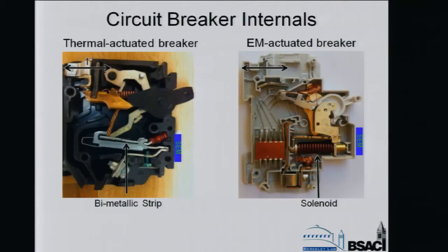Next, I'd like to show you what 2 main types of circuit breakers look like internally. On the left is what I'll call a thermal actuated breaker, and you can see here where our SEM sensor would be installed. There's a bimetallic strip, and when the current through the breaker becomes large enough, the heat dissipated in that bimetallic strip is enough to deflect it to the point where the breaker trips.